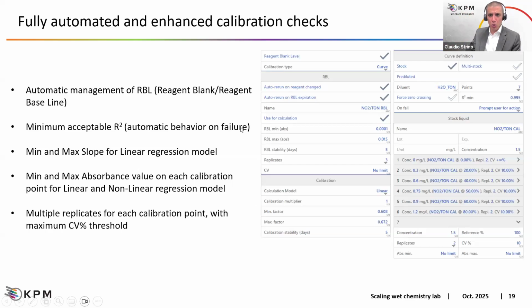When running the calibration, we can control the minimum acceptable R-square. Moreover, for linear regression models, we can control the minimum and maximum slope, because the R-square is an index for us to check the accuracy and reliability of the instrument in performing the automatic dilution for the different calibration points and to see the regression of those points. But the standard could be overestimated or underestimated. So the R-square is one index, but it cannot guarantee the goodness, the quality of our calibration.